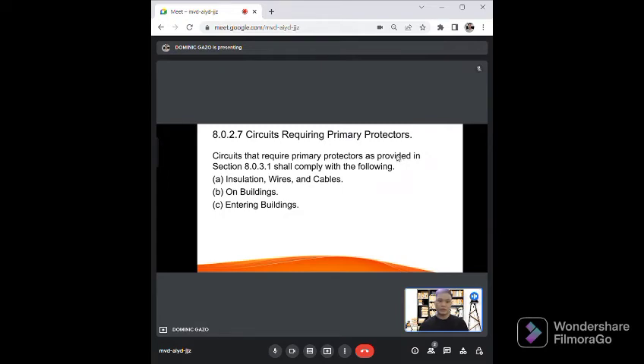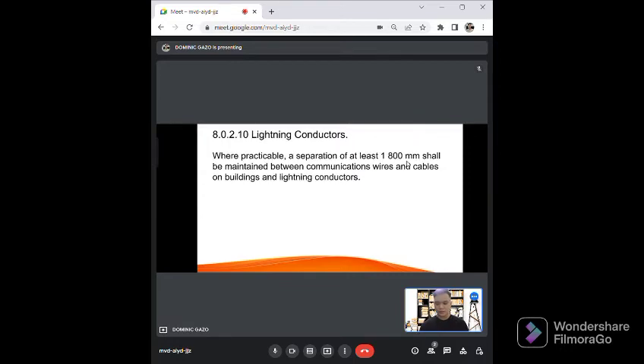And for entering buildings, where the primary protector is installed inside the building, the communication wires and cables shall enter the building through a non-combustible and non-absorbent insulating bushing or through a metal raceway. For Article 8.2.10, for lightning conductors, where practicable, a separation of at least 1 800 mm shall be maintained between communication wires and cables on buildings and lightning conductors.